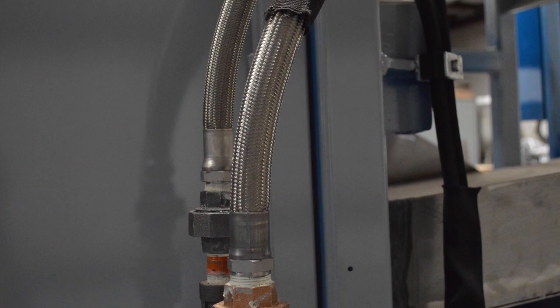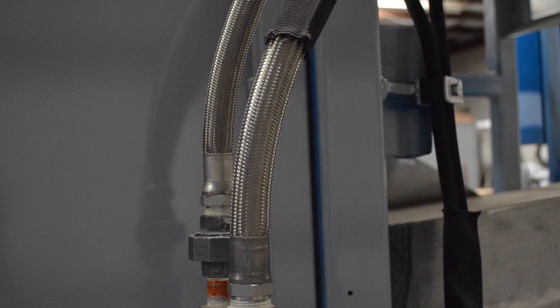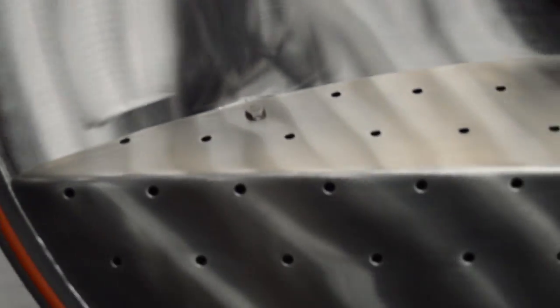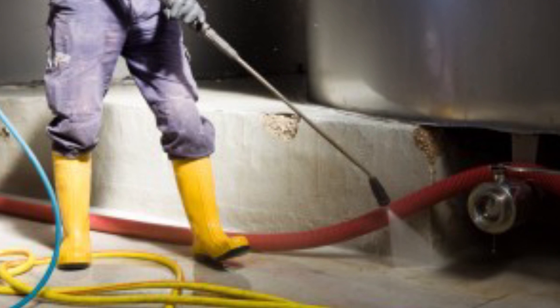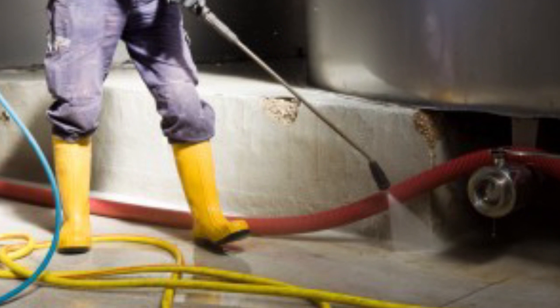Maintenance. Much of the maintenance on the SANIPAK is very similar to what is recommended for a standard compactor. In addition to checking fluid levels and hoses, the sterilizer O-ring door gasket requires basic maintenance attention. The door gasket is generally replaced 2 to 4 times a year, and the procedure takes only 5 to 10 minutes. Proper cleaning of the equipment and work area is the primary maintenance.